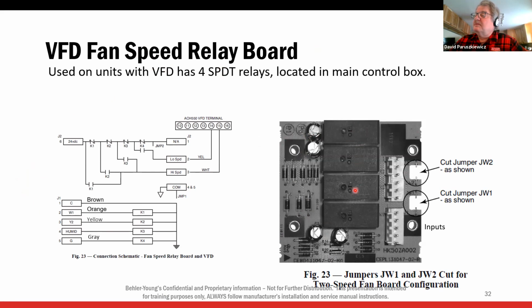So there's 4 relays, 1, 2, 3, 4. And here they are, K1, K2, K3, K4. Here's the contacts, normally closed, normally open, 1, 2, 3, 4. Okay, so there's my common 24 volts. And let's say I have a call for W1. Now, if you're paying attention, I said W1, heat will always be high speed. So on a call for W1, we energize the K1 relay. All right, the energize would be this relay here. So the little relay pulls in, this contact closes. Now, this 24 volts is DC coming from the drive, but let's see what happens. This goes here, through there, and we energize the high speed.